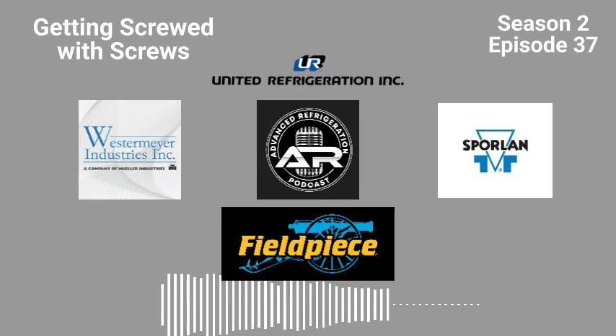The customer didn't even use them because they didn't even know they were there, because they're not on the coil drawings anywhere. So nobody included this in any of the controls. Because it's a CPC store, right? Yep. Case controller controlled? Nope. The box is just standard suction control. Okay. But it's just TXVs and on and off. All right. So then you'd have to run an analog output signal all the way over to the control. Are they like the MPass ones where they have their own 10 volt DC, where you could just jump it out and be 100% all the time?